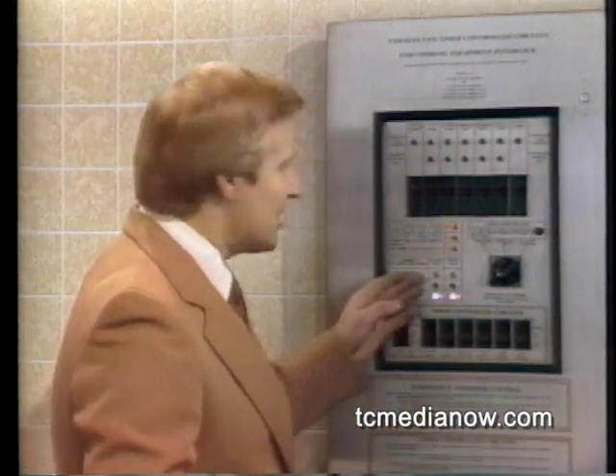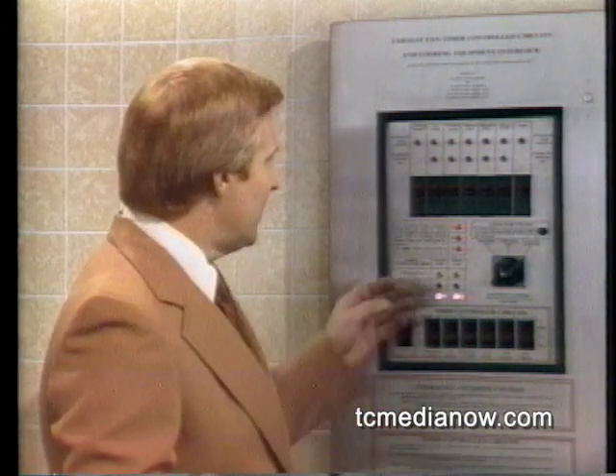And here are the status lights on the system panel that give you information about what the system is doing at any given time as it progresses through each programmed 24-hour cycle. Remember that the system splits the store into two heating and cooling zones, the kitchen and dining area, and sets preconditioning, daytime, and night setback modes for each zone independently. Now, let's run through the daily routine of the system and how it operates. Just before the first person is due to arrive at the store, an hour and 40 minutes prior to opening, the auto load program turns on half the parking lot lights. 40 minutes later, half the soffit lights will come on.